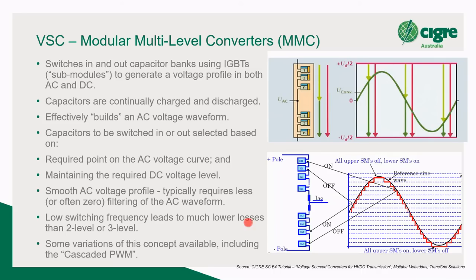And you can imagine the control system is a pretty busy device right now, because it is constantly measuring the voltage across all of these capacitors. And it's constantly working out what's the best combination to make up my 200 kV on the DC side, but also to switch in the right amount on the positive and negative side to create my point on the AC voltage waveform. One of the benefits of this technology is that the AC voltage waveform is actually quite smooth.